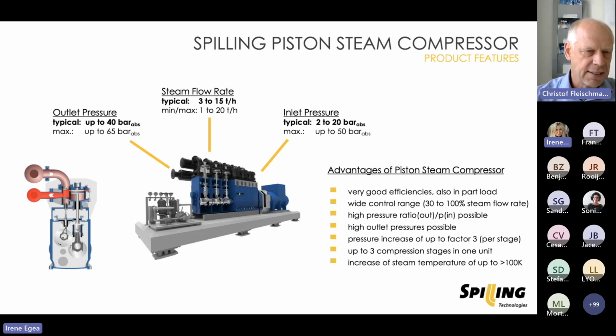On the outlet side, like I've mentioned in the slide before, we reach with our standard units up to 40 bar. This corresponds to about 250 degrees Celsius saturated steam temperature. The typical mass flows through these machines is 2-3 tons per hour up to 15 tons per hour. In some cases, we can also reach 20 or even 30 tons per hour.